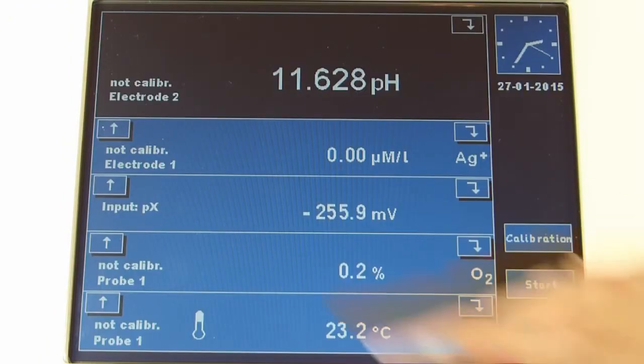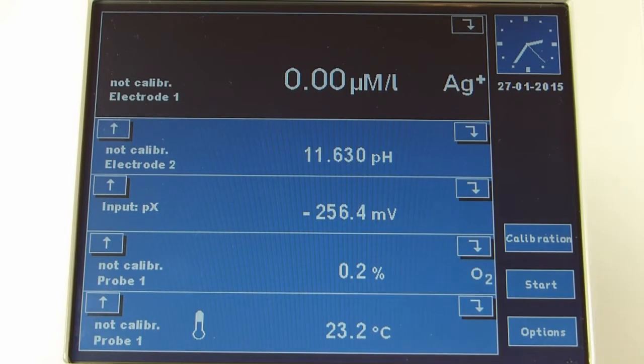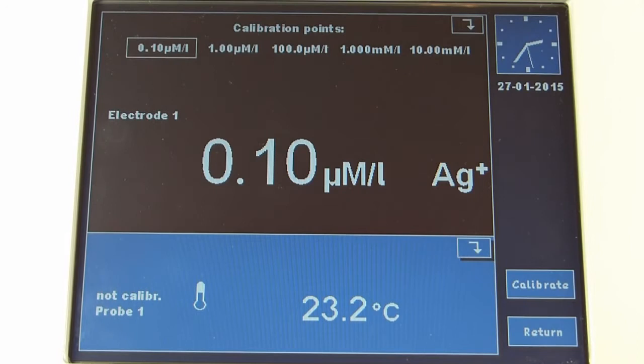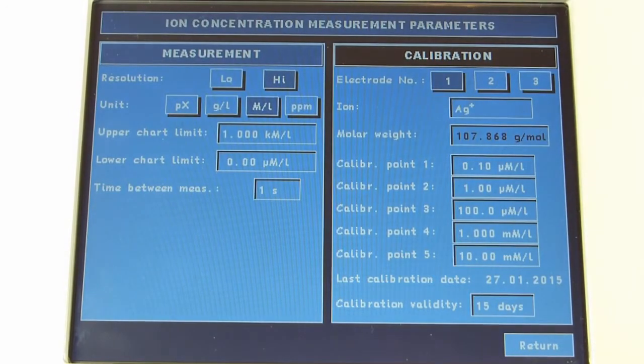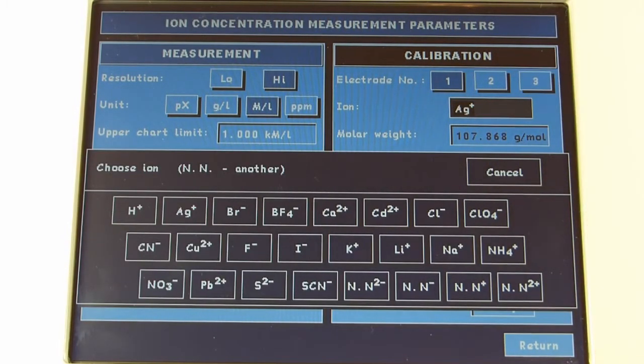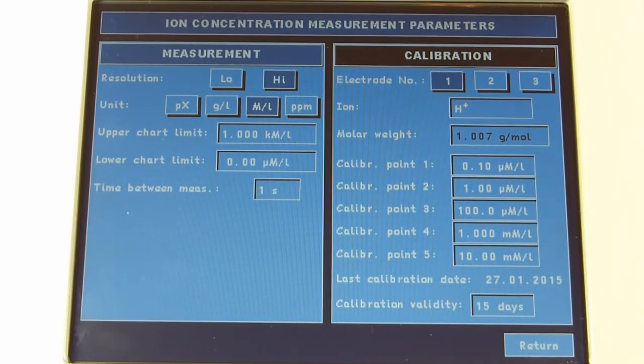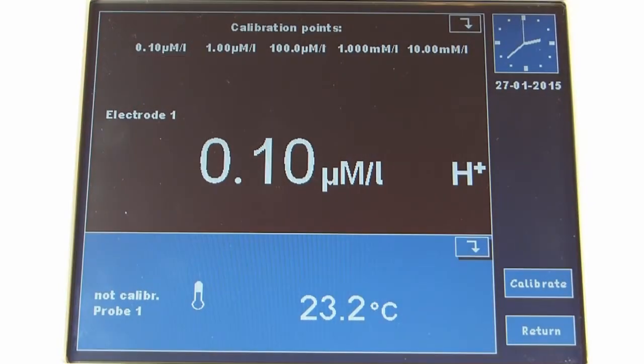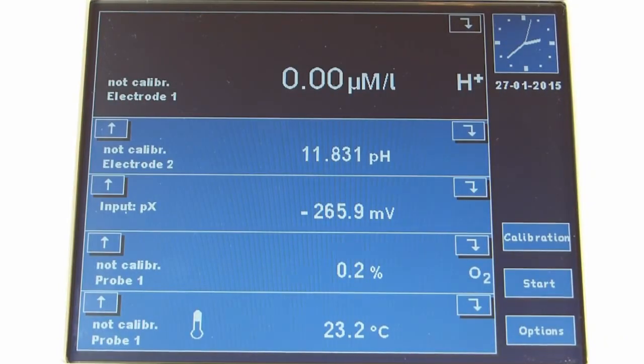To make the calibration in the ion selective measurement, press and hold the calibration button. Calibration mode. After choosing the parameters of calibration, calibration parameters, choose the symbol of the ion to measurement of which your ion selective electrode is designed, so that the molar weight and valency would be set automatically. In this case, the unit conversion is also automatic. Calibration mode. Measuring mode. It is possible to make simultaneous pH and ions measurements.